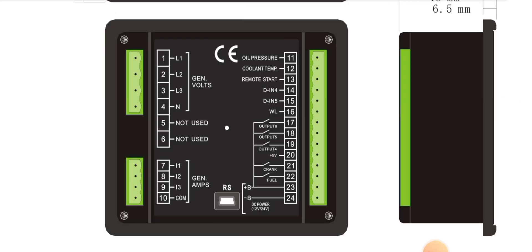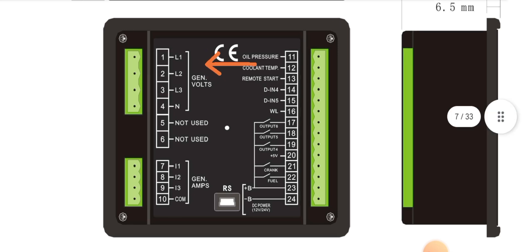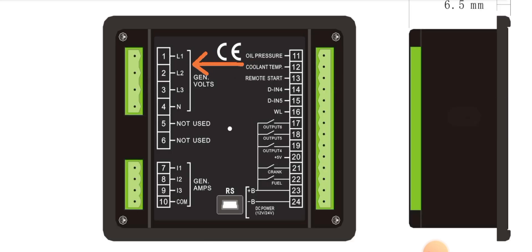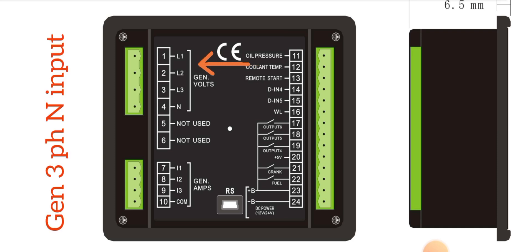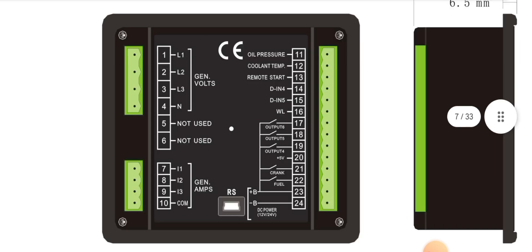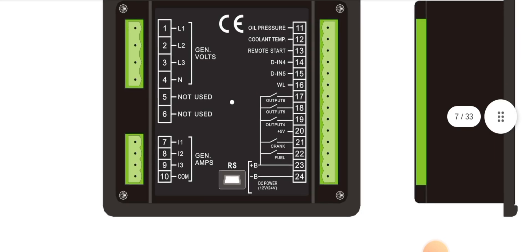Pin 1, 2, 3 is the gen volt, and pin 4 is the generator neutral input. L1, L2, L3, and N — L1, L2, L3 are the three pins and three-phase inputs of your generator, and pin 4 is neutral. Pins 5 and 6 are not used.